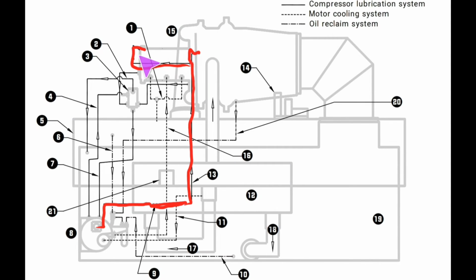So this back line feeds your rear bearing on the motor, right? And then the front line feeds the front bearing, and specifically, more importantly, the journal bearing. We can go ahead and talk about that a little bit now. So one of the things that is real critical is the oil temperature. These don't have a super tight parameter window on the oil temperature side, but you have to be really careful with it.